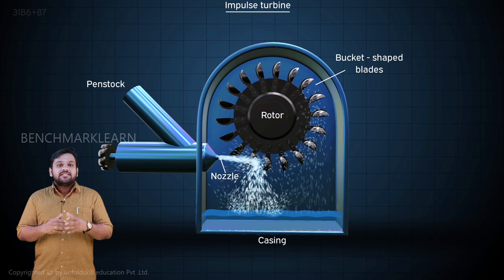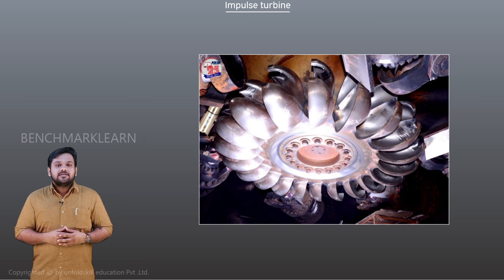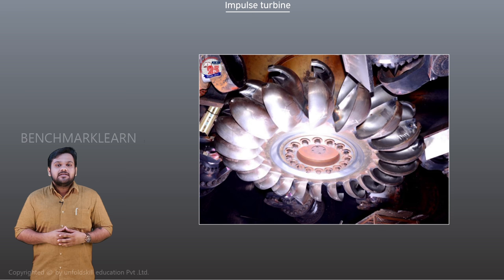The water strikes the wheel tangentially, so this is also called a tangential flow turbine. Impulse turbines are suited for high head and low discharge of water. The Idukki project in Kerala uses six Pelton turbines, each with a capacity of 130 megawatts and a rated head of 660 meters.